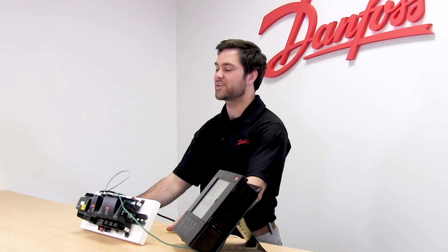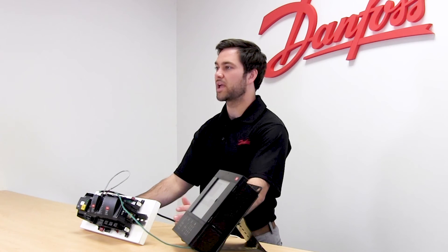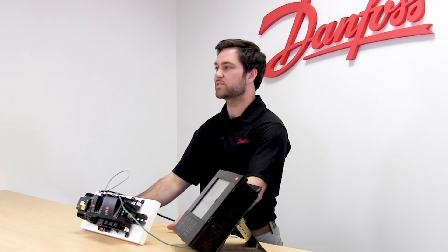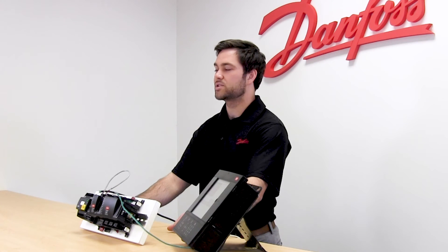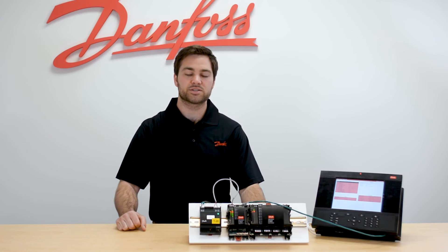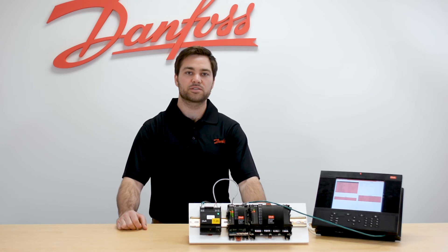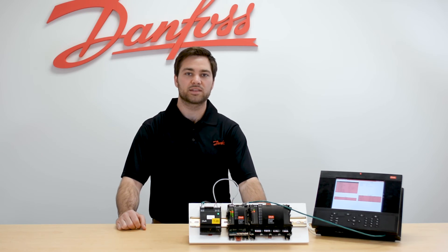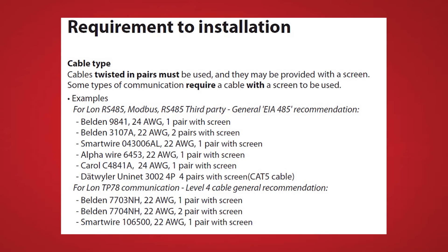The last two major things to check for are the overall length of your wire, which should not exceed 4000 feet per run without a repeater, and your communication cable type. For TP78, our older style equipment, this follows the level 4 cable specifications. For the newer RS485 equipment, we follow the general EIA RS485 guidelines. As you can see on the screen, here are some additional specifications we require for the different wire types.